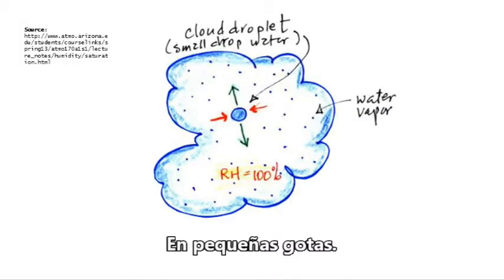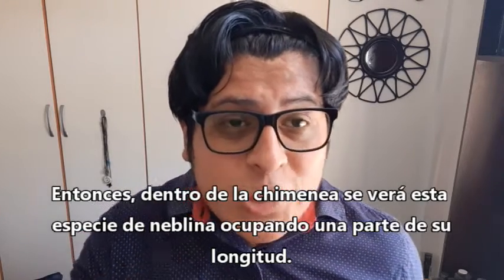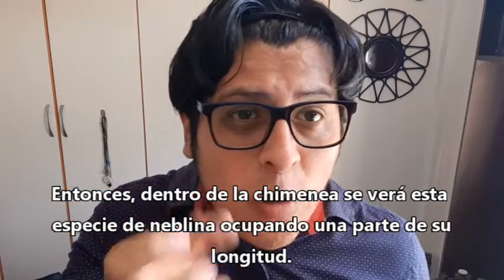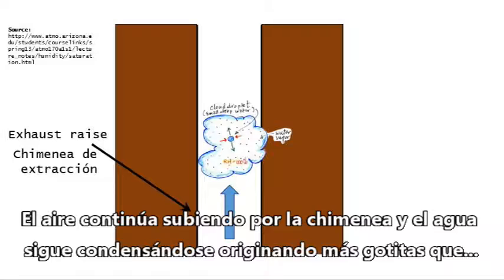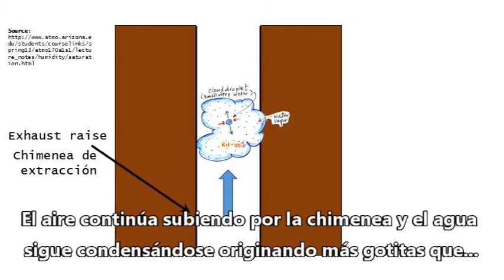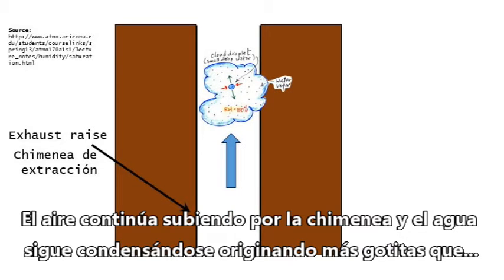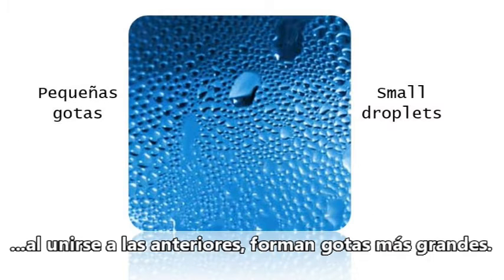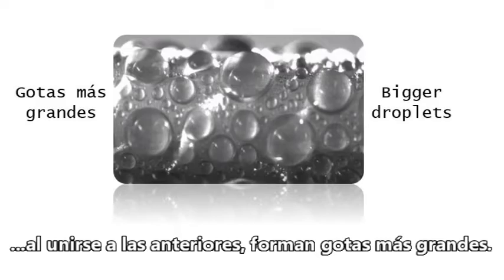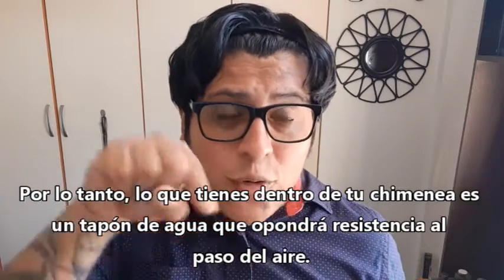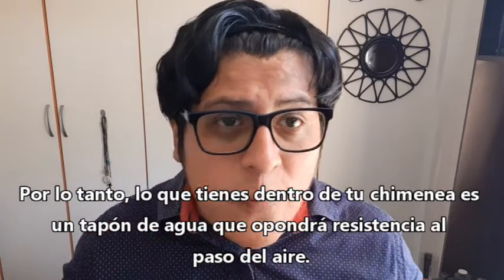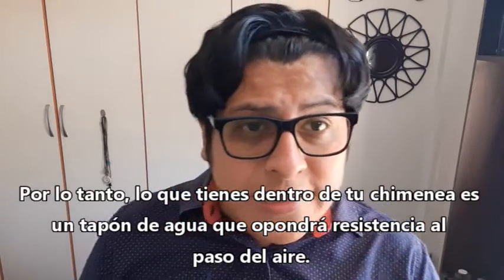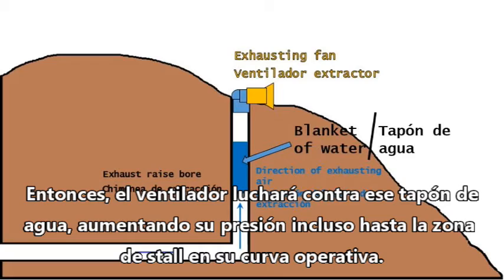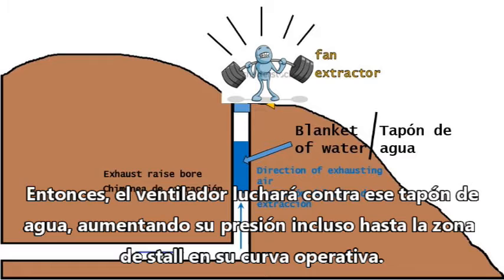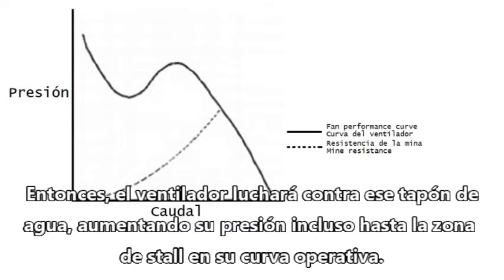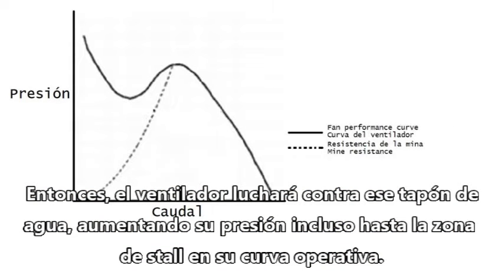In really small droplets. So inside the raise you will see this kind of fog formed at some portion of its length. The air continues to ascend inside the raise and water continues to condense, resulting in more small droplets which, joined to the previous ones, create bigger droplets. So what you have inside your raise is like a blanket of water that is going to create resistance to the flowing of air. Thus, the fan will try to struggle against that blanket of water by augmenting its fan pressure even to the stall zone in its operating curve.